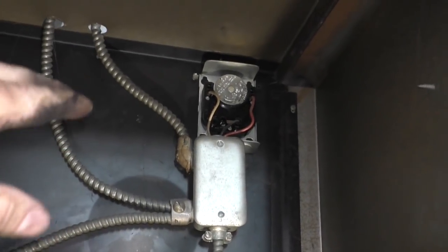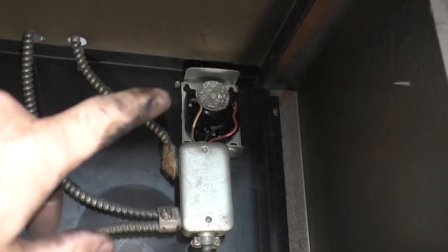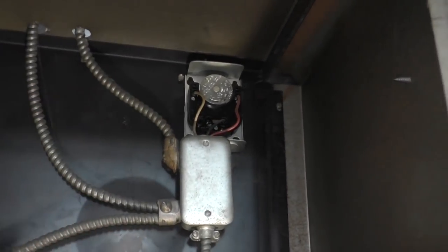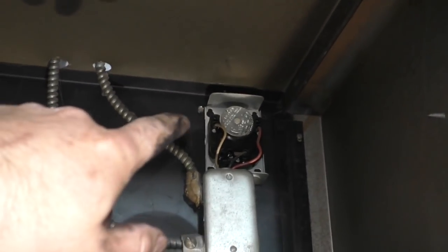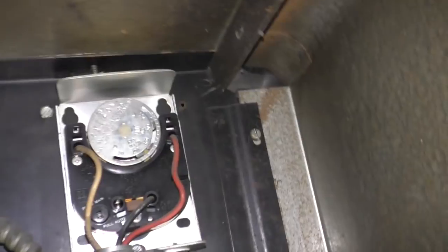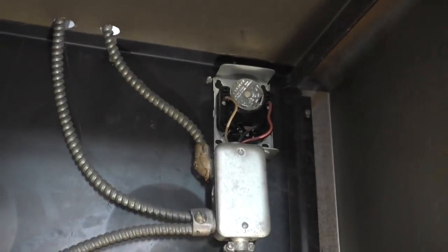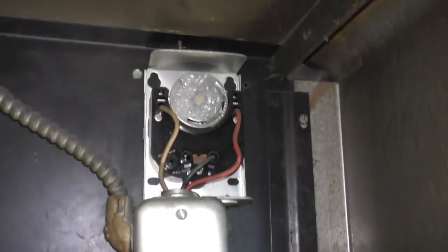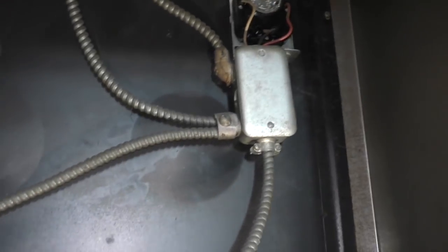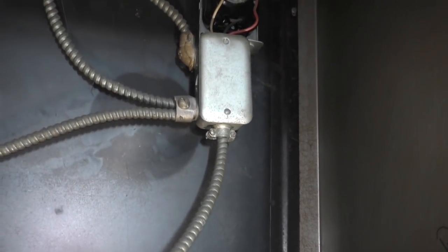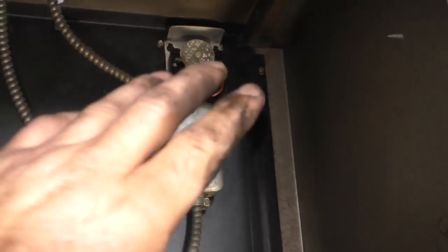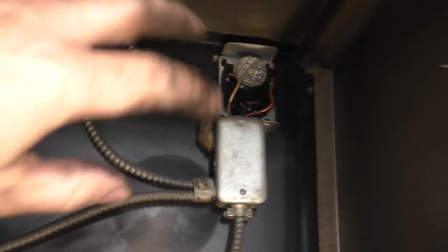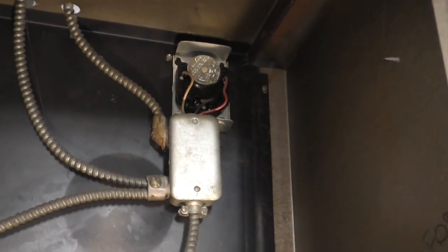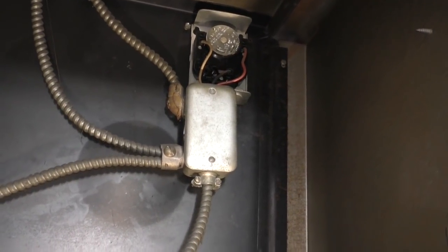If the temperature continues to rise, what's going to happen is it'll reach what's called thermal limit cutout. That's locked at around 225 degrees Fahrenheit. If it hits that, it's going to shut off the burner. Under normal operation, that should not happen. It should stay somewhere between the fan-on set point and a few degrees higher from there, and that's where it should kind of live. But when it reaches the thermal cutoff, that tells you there's something wrong.